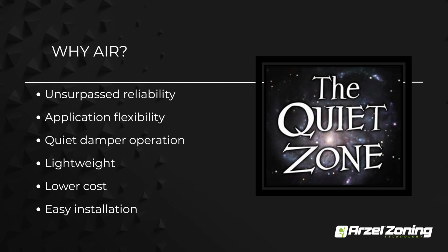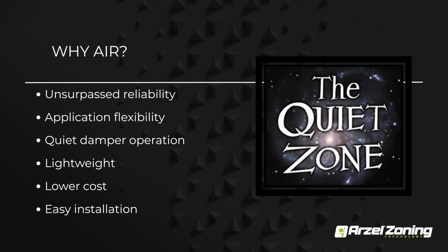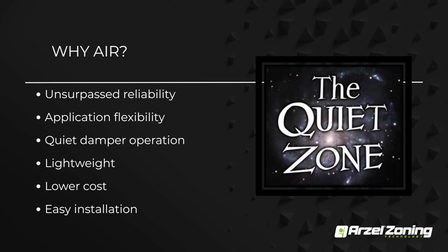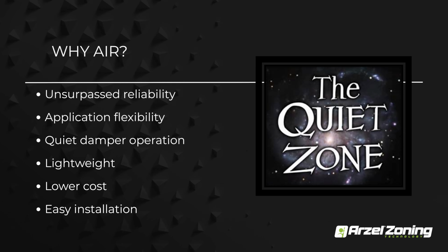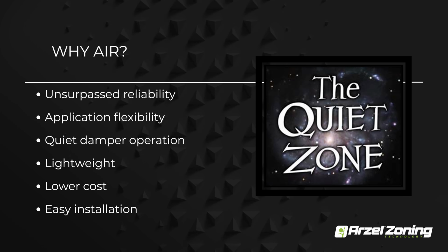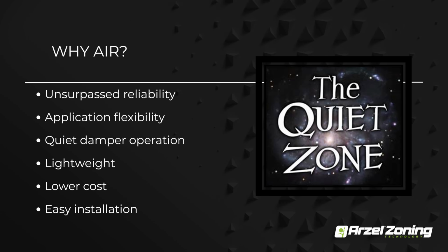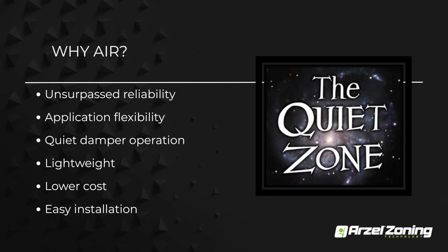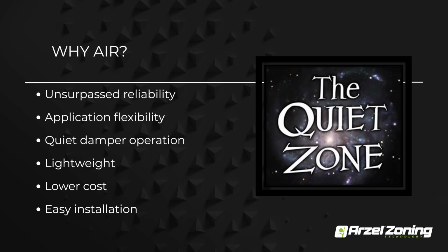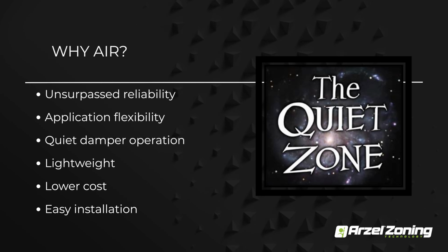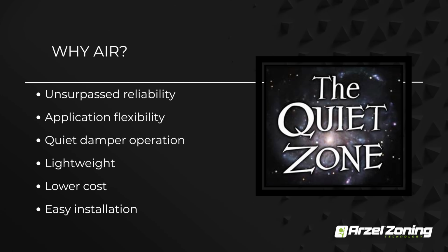Then, why do we use air? Essentially, it's just due to reliability. The first thing to fail on most of your motorized systems out there is going to be that damper motor. By getting away from having those motors, our dampers are very reliable. There's absolutely no noise on the damper at all because there is no motor. And it gives you a lot more flexibility on installation. You can mix and match these dampers. You don't have to worry about additional transformers or additional components. Everything comes with that panel and your dampers, you install it, and there are no additional accessories that you need. So it's a pretty easy design system.